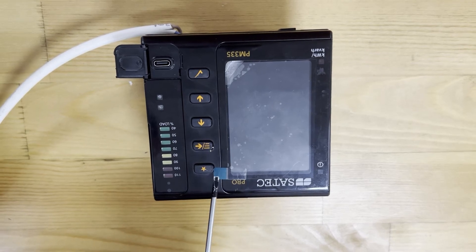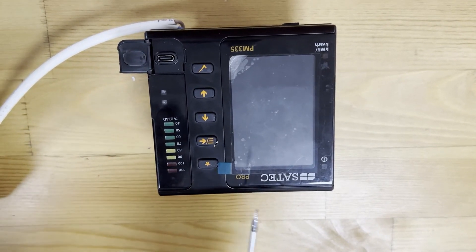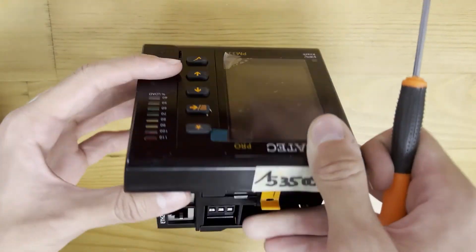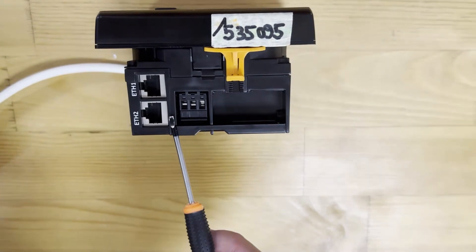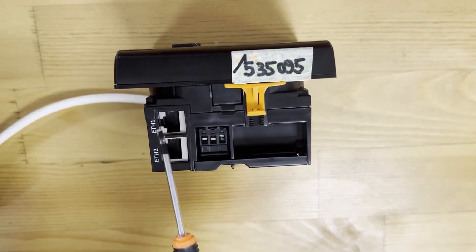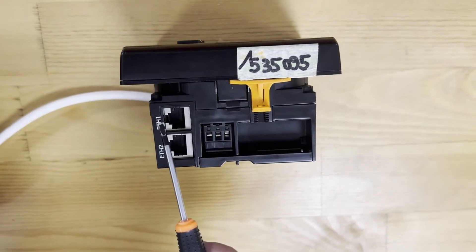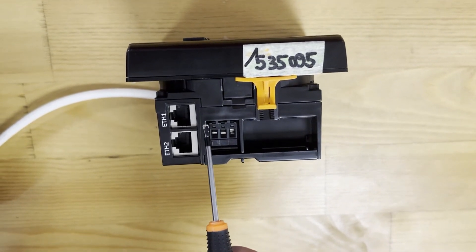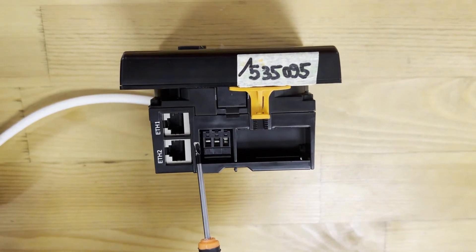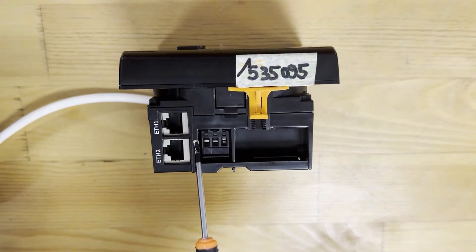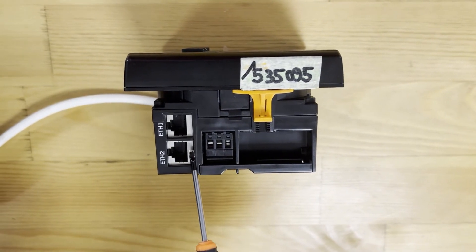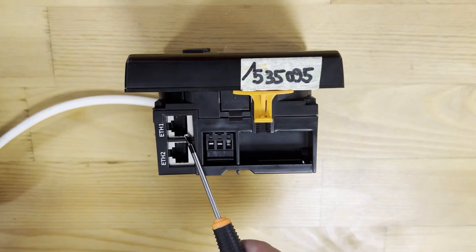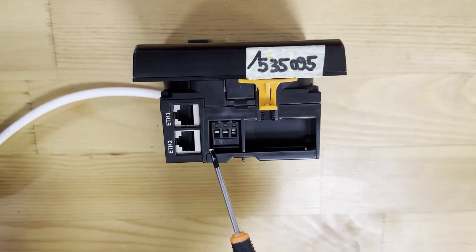Let's talk about the Ethernet ports. These Ethernet ports allow the pro-meters to be directly connected to a local area network using the TCP/IP protocols. No device identification is required when connecting via the Ethernet ports. The SATEC pro-meters respond to any device address and return the received address in the response message. The two Ethernet ports can either be configured for separate and independent Ethernet port or used for daisy chain configuration.